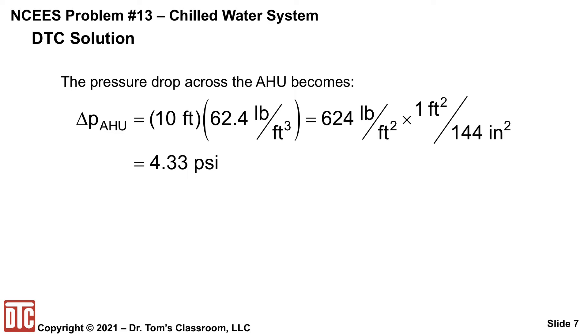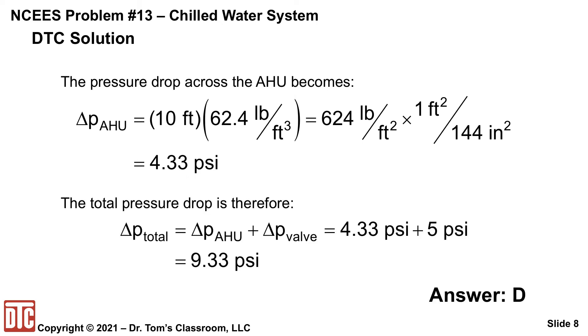And this is given in 10 feet of water. So you've got 10 feet times 62.4 pounds per cubic foot. So you get 624 pounds per square foot, which you need to convert to psi. And when you do that, you get 4.33 psi. And so just add the 5 psi for the valve and you get 9.33 and that's answer D.